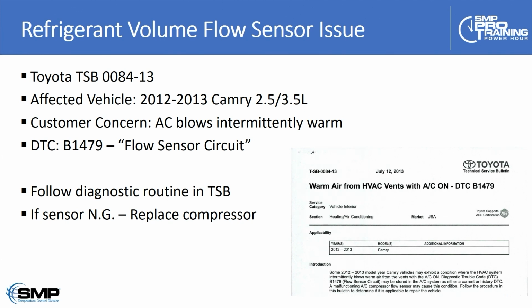I often get asked, can the sensor be replaced separately? The problem, first of all, is that I see a lot of inexpensive online sensors that do not work. They output a fixed voltage, and the voltage does not change as the refrigerant volume flow changes, so beware of that. Also, sometimes it can be difficult to determine whether it's a problem with the sensor or a problem with the plunger, the magnet and the springs underneath. By the time you've recovered the refrigerant, with all the labor and refrigerant expense involved, it's usually more cost effective to replace the entire compressor as an assembly.